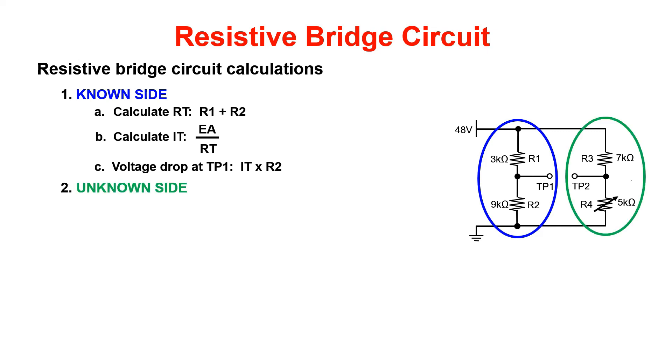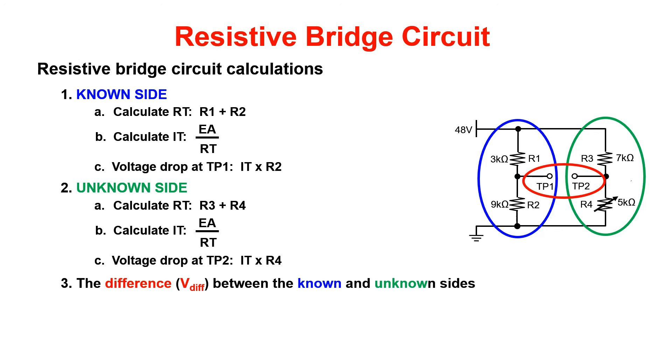Rinse and repeat for the unknown side using R3 and R4 to calculate RT. Now that you have the voltages at test point 1 and test point 2, perform the calculation TP2 minus TP1. And voila, you're done.